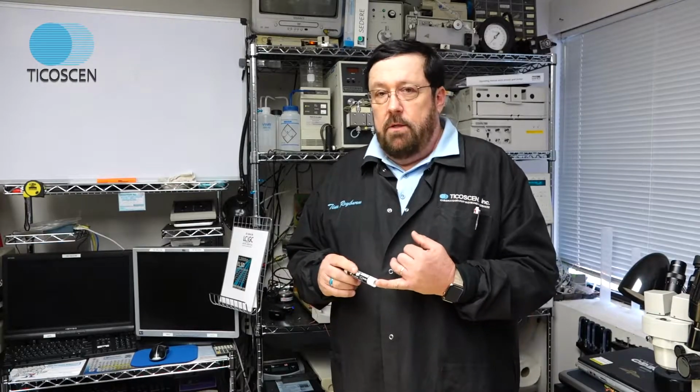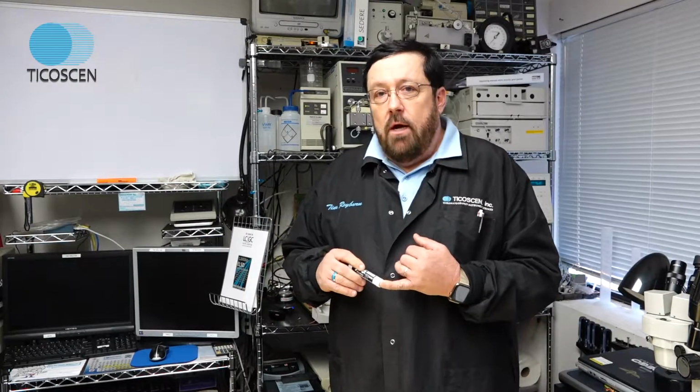What are the different kinds of contamination that an ELSD will have to contend with? I'm going to talk about some of the major areas I see repeatedly across the country. One is your gas supply.